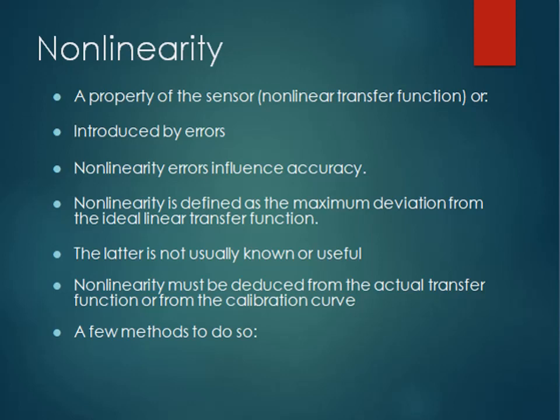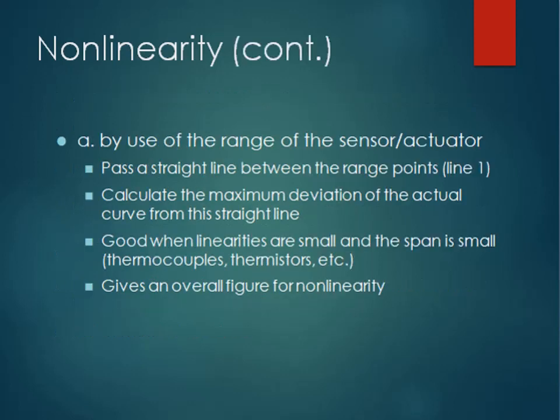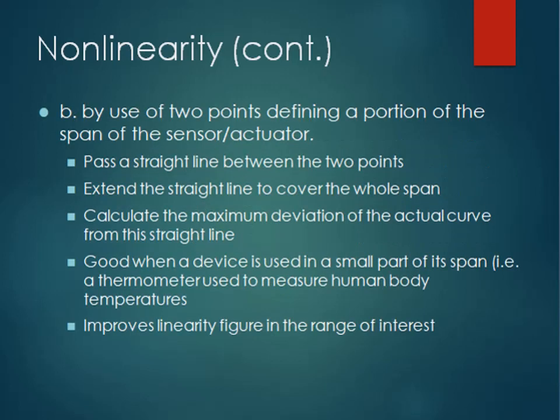There are a few methods to do this. First is by use of the range of the sensor or actuator. You just pass a straight line between the range points and calculate the maximum deviation of the actual curve from this straight line. It is good when nonlinearities are small and the span is small, for thermocouples and thermistors especially. It gives an overall figure for nonlinearity.